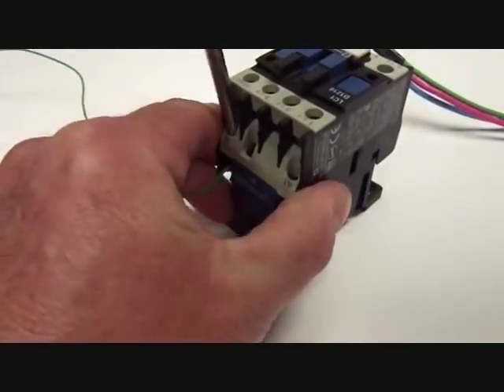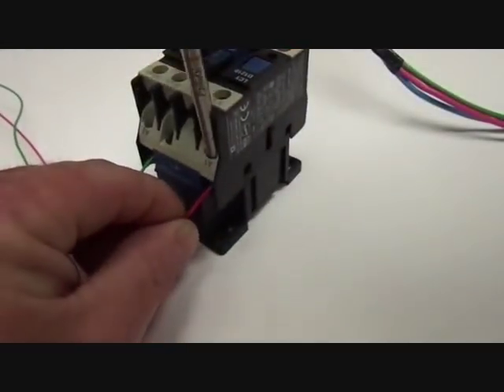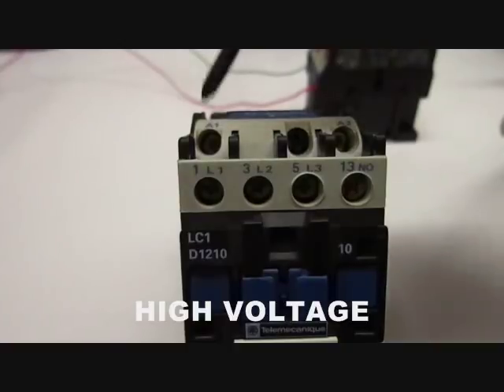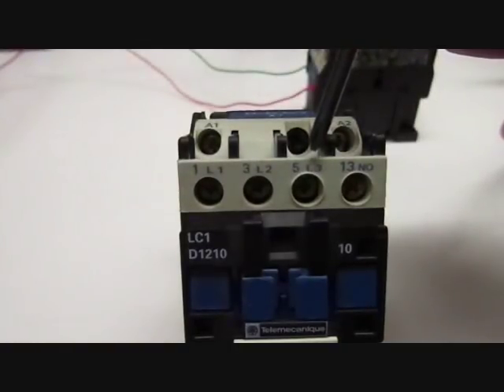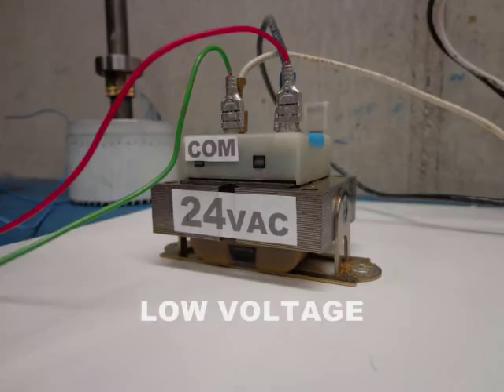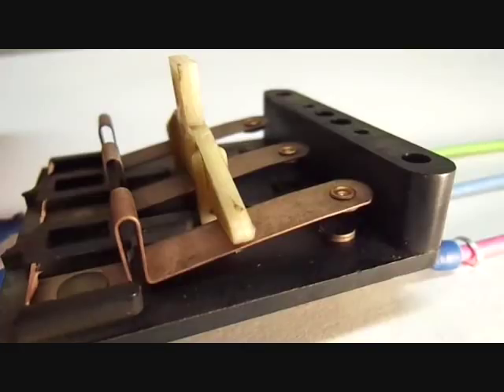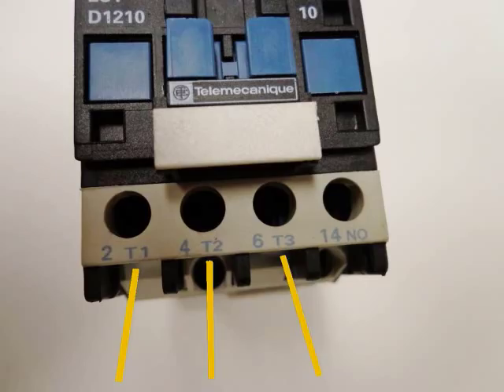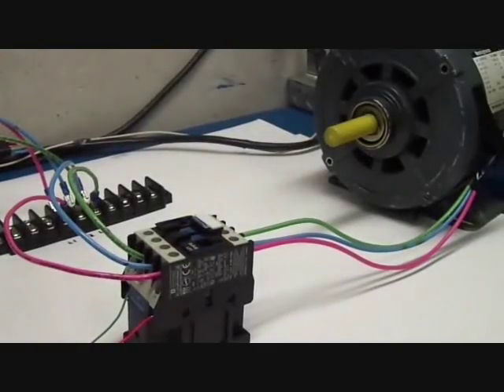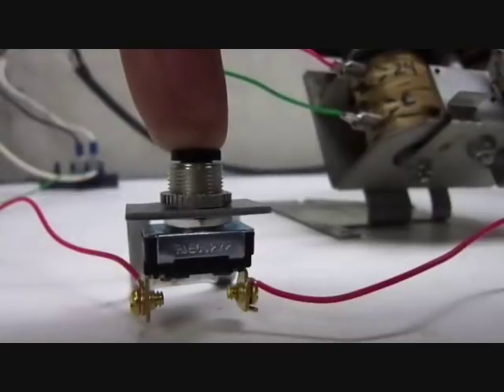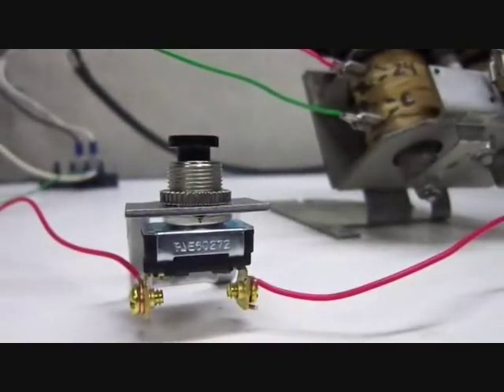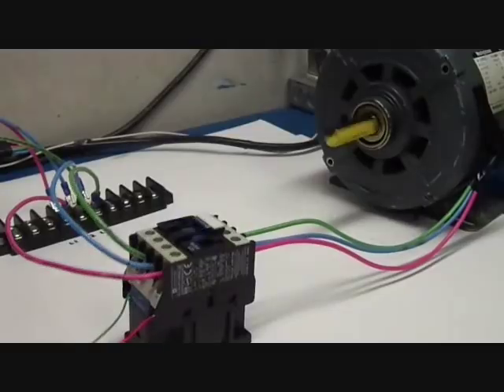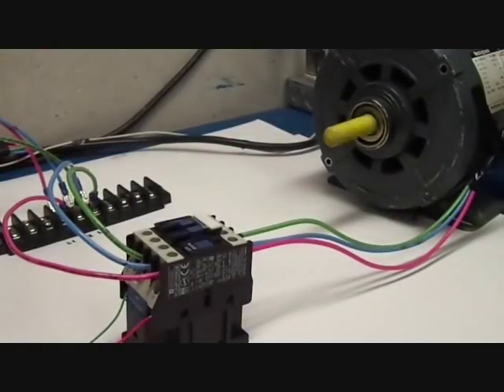Polarity on the coil terminals doesn't really matter. I'm going to bring my three phases from the breaker panel into the terminals labeled line 1, 2, and 3. Now we have constant power coming into the contactor, and when I connect 24 volts to the coil, it will allow that power to go through the main contacts to terminals T1, T2, and T3. I don't know what T stands for, but I know it gets hooked up to the load. And there you have it. I can use a cheesy little single pole switch that's only rated for a quarter of an amp to run a three-phase 460 volt motor that runs at 20 amps.